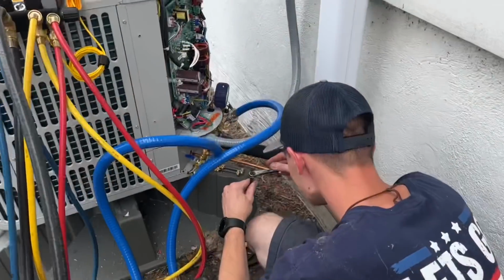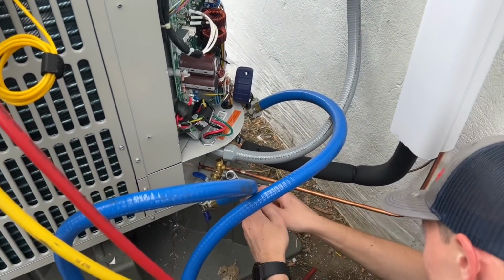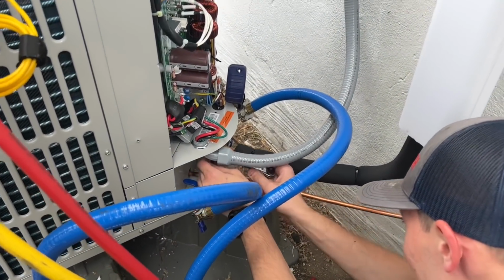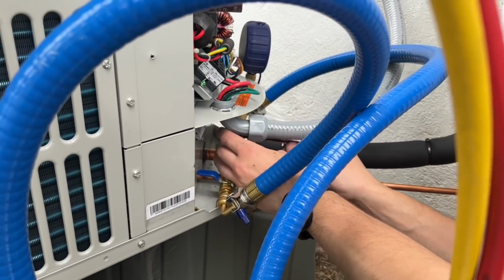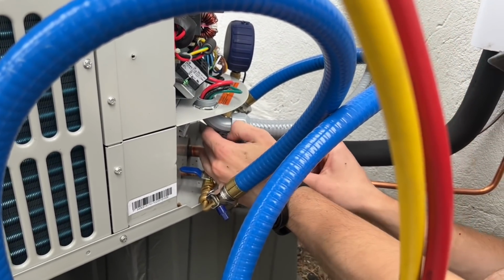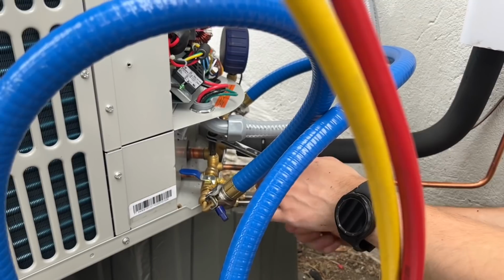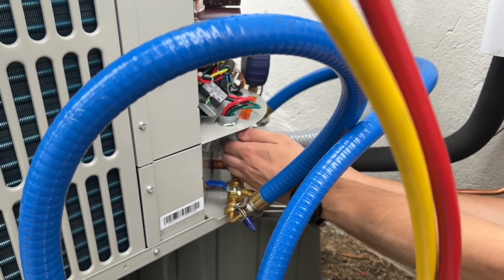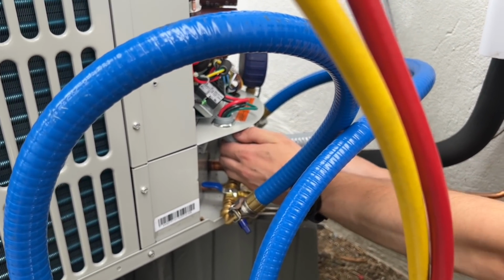Now Daniel's going to open the liquid side service valve. We have a yellow jacket ratcheting wrench there. It's the liquid side we open up first, right? Yeah, because that's the natural flow, in cooling mode.